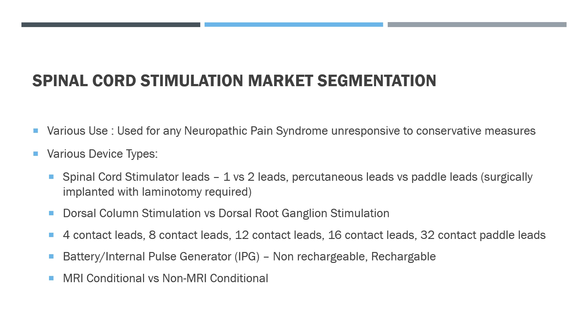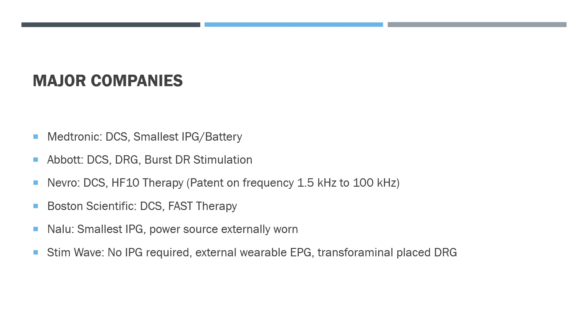In terms of the major companies, there's Medtronic, which provides dorsal column stimulation. It also has the smallest IPG and battery. Abbott Neuromodulation, which provides DRG and their novel therapy Burst DR. Nevro Therapy, which is dorsal column stimulator as well, which has HF10 therapy, has a patent on frequencies of 1.5 kilohertz to 100 kilohertz. There's Boston Scientific Therapy, which also has just dorsal column stimulation. Nalu, which has the smallest IPG, and their power source is externally worn, so you have no large battery implanted. And StimWave, where there's no IPG required. There's an external wearable external pulse generator and a transforaminal placed DRG. Now Bill will talk about market forces in spinal cord stimulation.